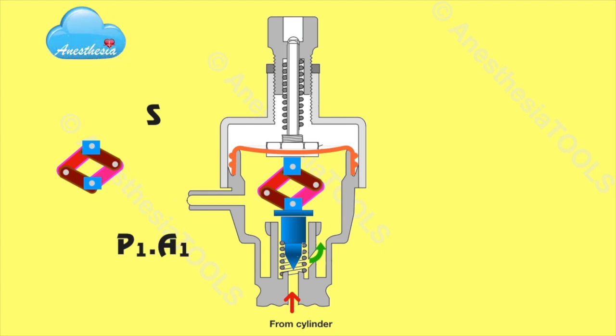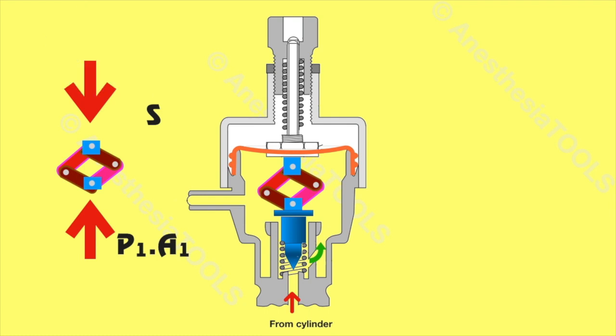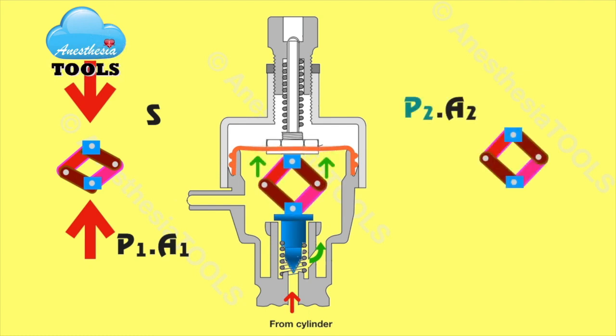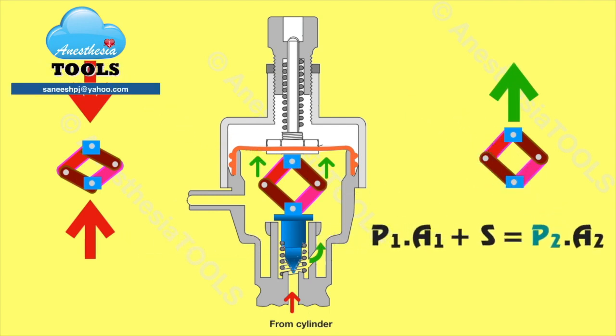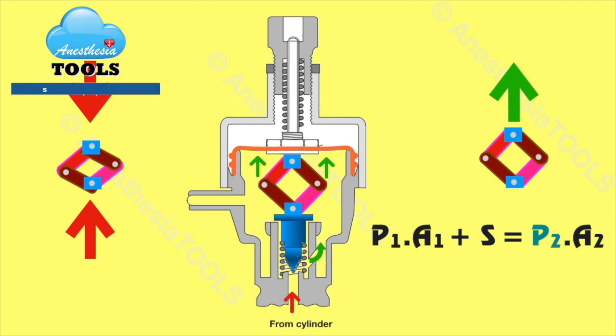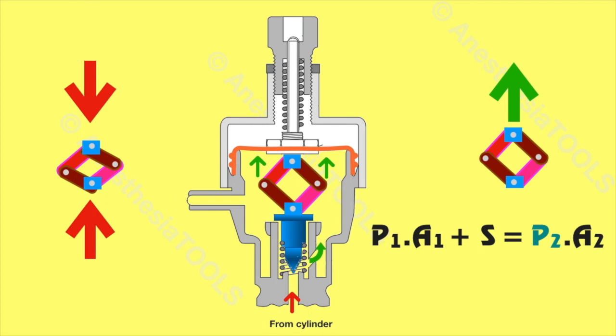At equilibrium, the forces pushing the lazy tongs to open the valve are P1 × A1 and the spring tension S. The balancing force pulling the lazy tongs to close the valve seat is P2 × A2, the regulated pressure acting on the diaphragm. The equation is: P1 × A1 + S = P2 × A2. Thus the outlet pressure is maintained more or less constant, since S is significantly high compared to the varying value of P1 × A1 as the cylinder is used up.